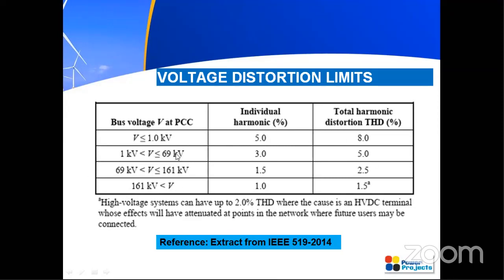Similarly, for different voltage ranges, from 1 kV to 69 kV, 69 kV to 161 kV, and up to all the voltages higher than 161 kV, the individual harmonic limits and the total harmonic distortion limits are given. And there is an exclusion: when you go for an HVDC terminal, instead of 1.5, 2% is also allowed. This is the note. So this is about the voltage distortion limit.